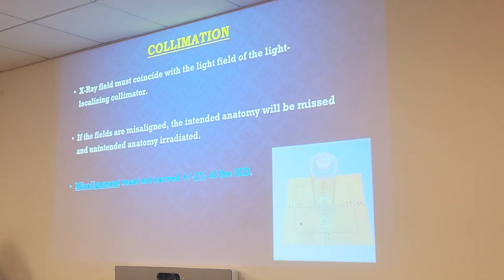And the way they test this is, you see these dots on the outside, right here? If the collimation is exceeding these two dots here in the corner, meaning they're outside of these 4 squares and they're on the edge, that means your collimator needs to be readjusted. That's for the medical physicist to do. Okay? Plus or minus 2%, that's the 2 lines. That's in the box.